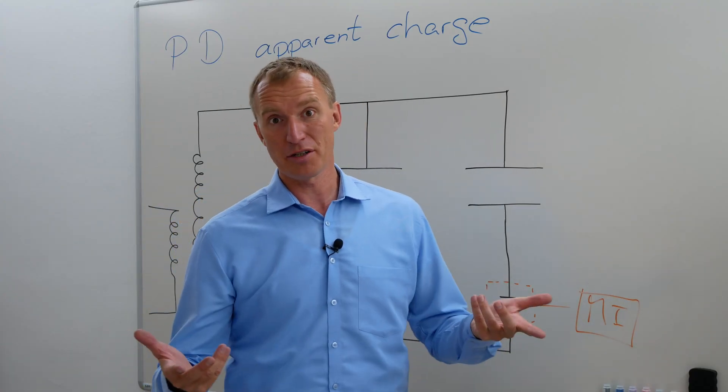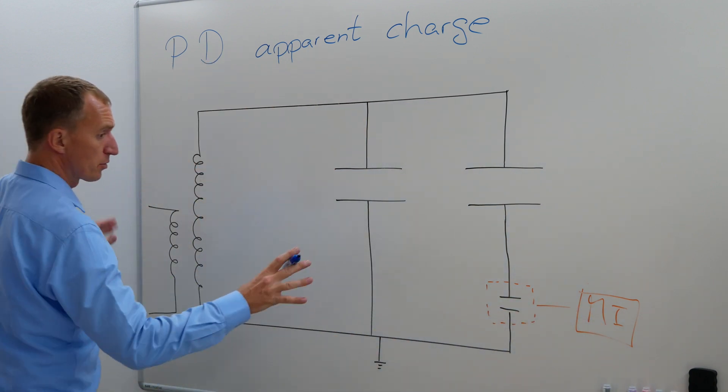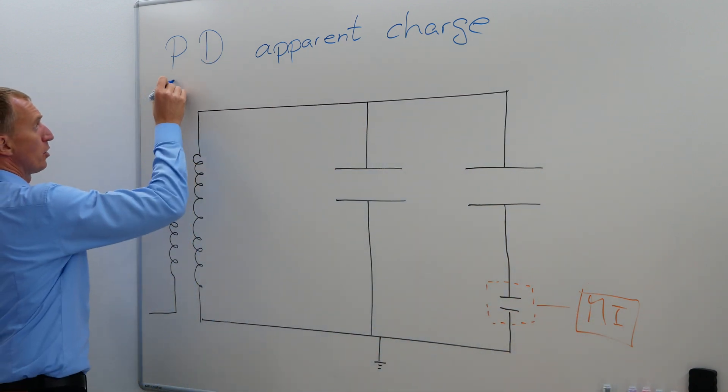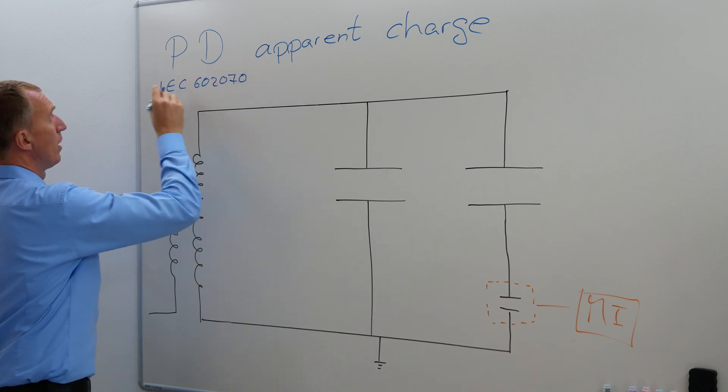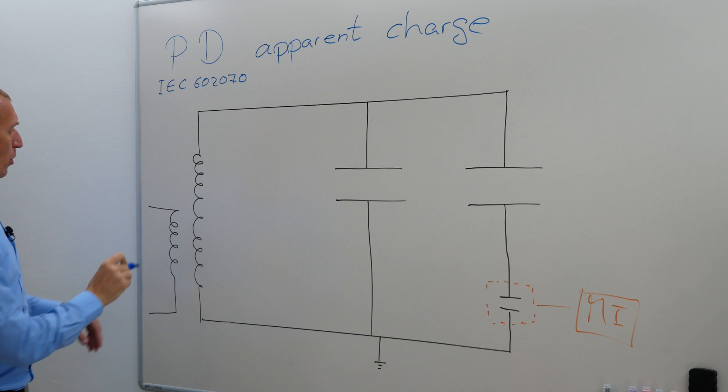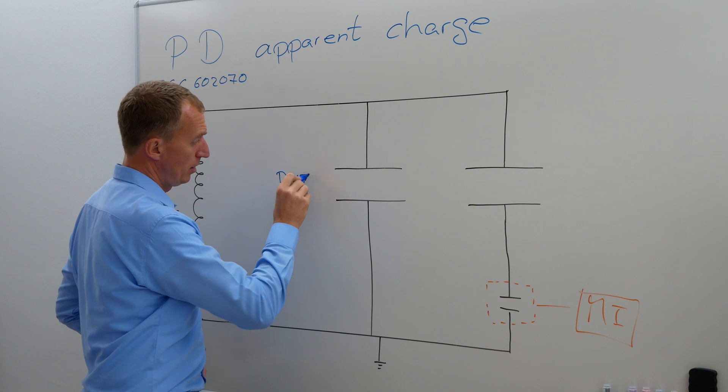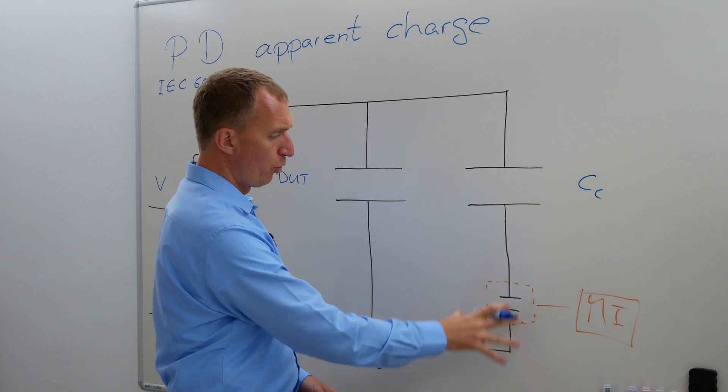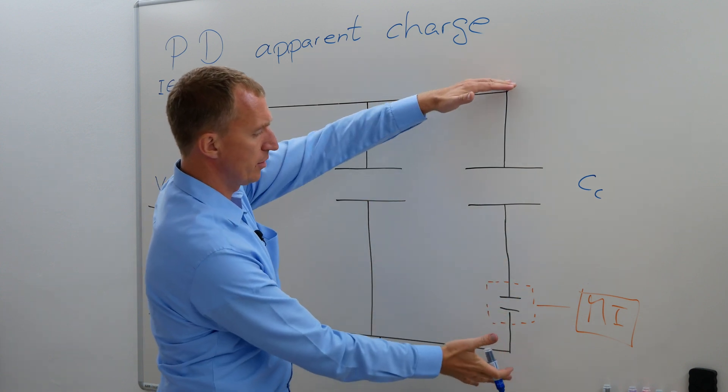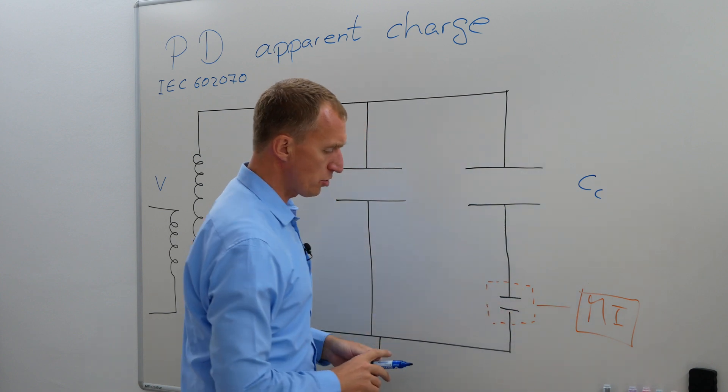In order to measure partial discharges, we need a measurement setup and behind me I've prepared something already. This is our diagram of a measurement setup. This is very close to what we see from the IEC 60270. We have a voltage source here, a high voltage source. We have a device under test, that's our test object and we have a coupling capacitor here. And furthermore, we have our low voltage capacitance here, this is our capacitive divider in order to measure with our measurement instrument to measure partial discharges.